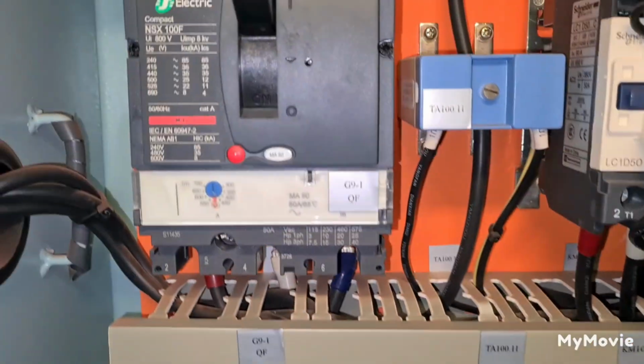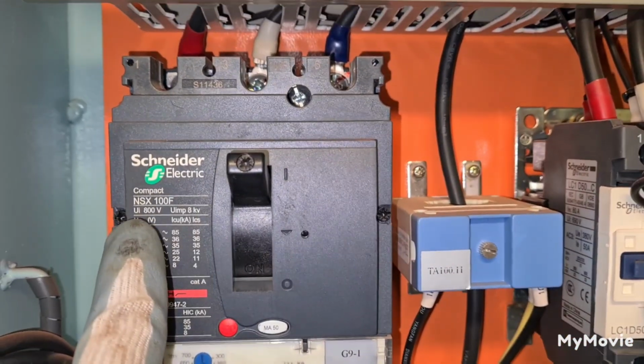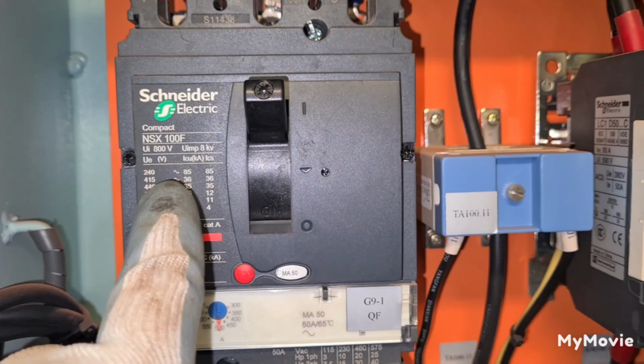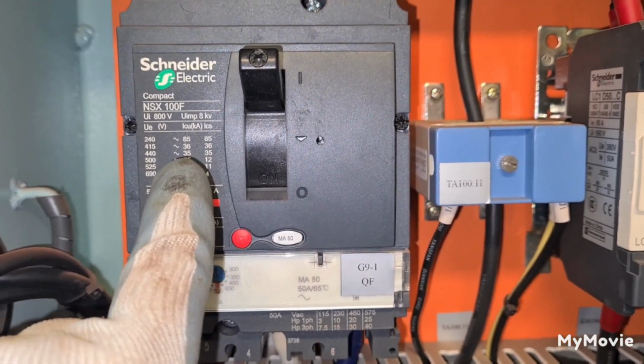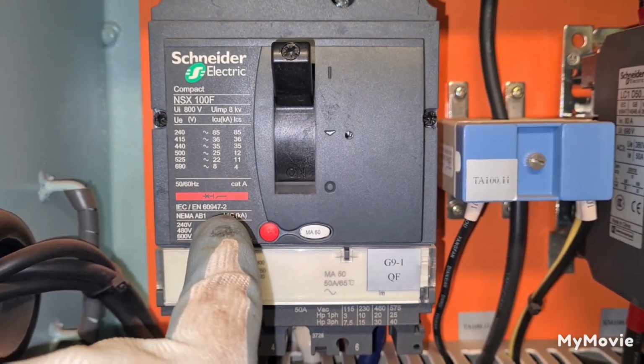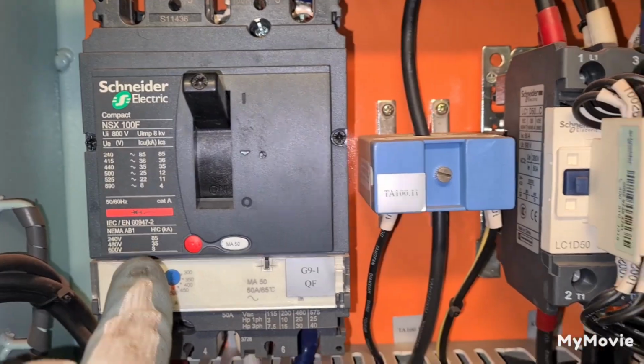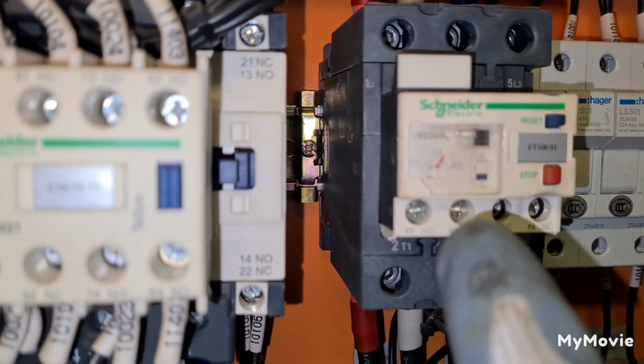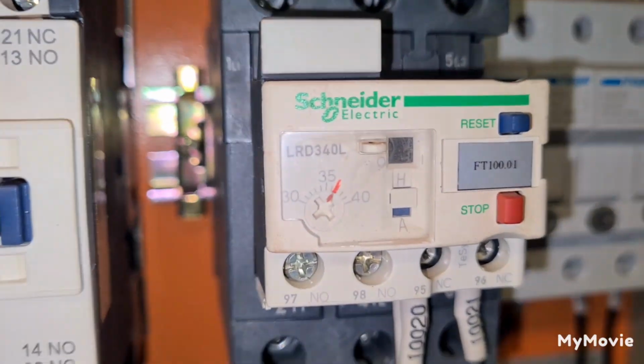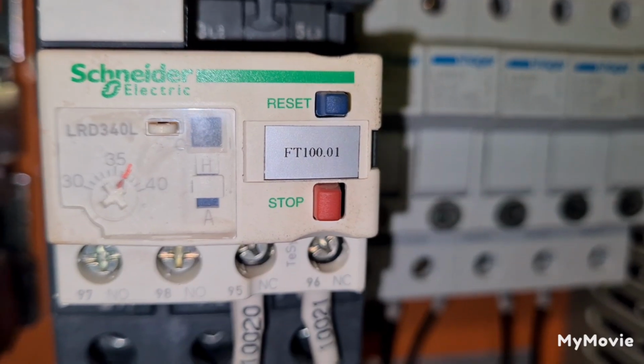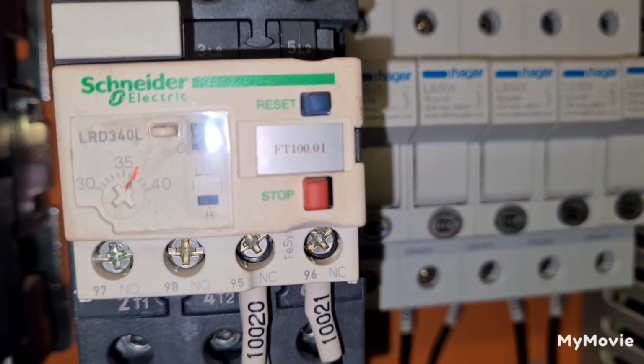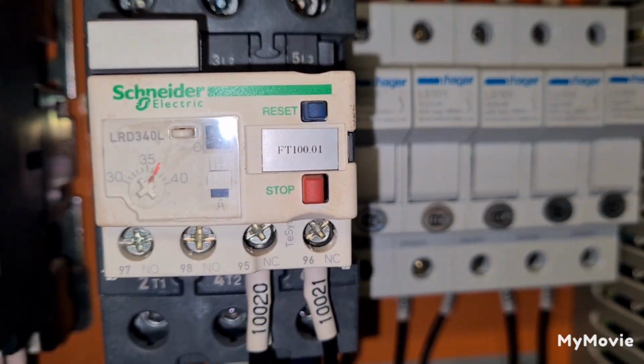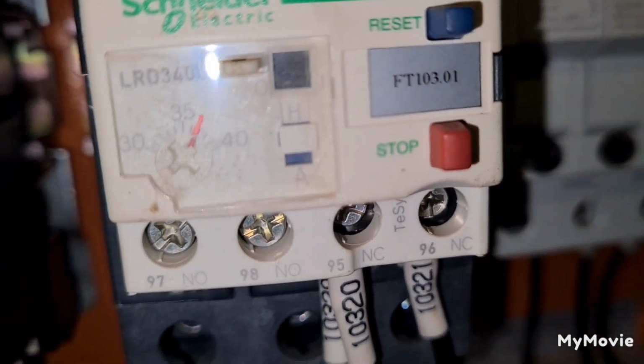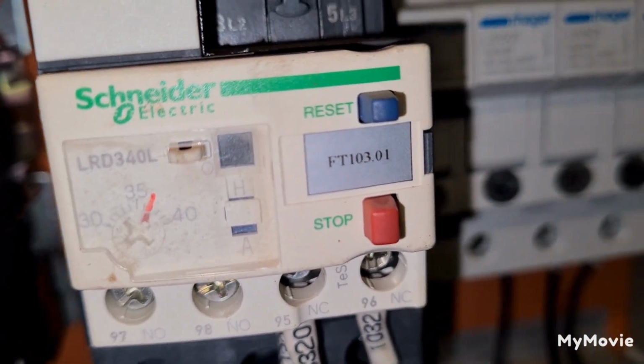See, and it has type NSX 100F, that is the ampere frame, 800 volts, Uimp 8 kilovolts, and category A. So the setting of my overload relay is set at 30, how much is this? 38 amperes, or 38 amperes. So this one, you can check the setting, 36.